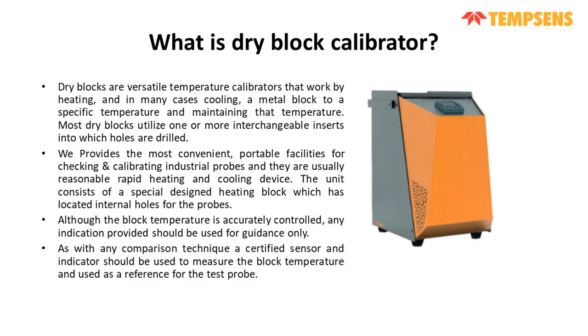Dry block calibrators are used for the calibration of RTDs and thermocouples. In this we have a metal block with previously drilled holes according to your requirement, which can be customized as well. You just put that metal block in the calibrator, then put the sensors, and it will calibrate according to the master. These are versatile temperature calibrators that work by heating, and in many cases cooling, a metal block to a specific temperature and maintaining that temperature. They can utilize one or more interchangeable inserts into which holes are drilled, and in those holes you put your RTDs and thermocouples.